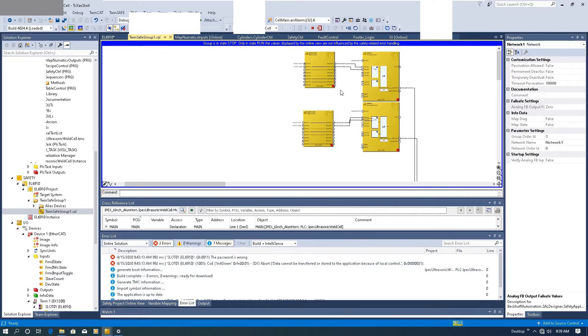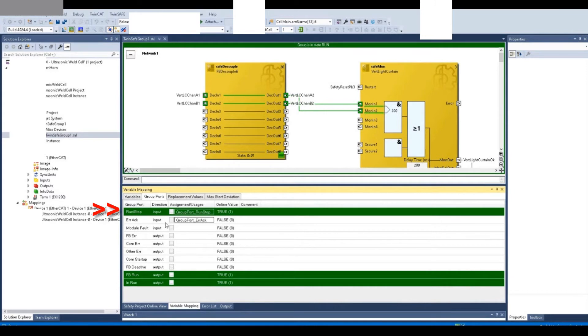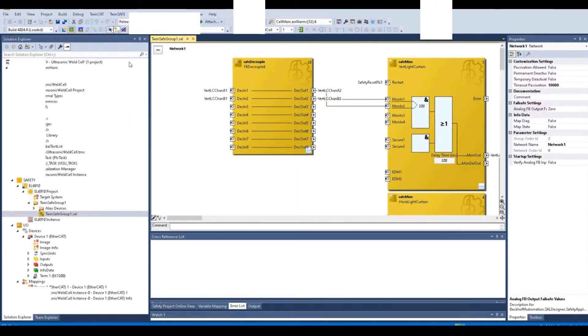Once you go online, if you see all the function blocks show a red flag, on the top area if it shows 'Stop' you must check the run-stop signal for your safety controller. This signal must be on to let your safety controller run. Keep in mind that the run-stop signal comes from the standard PLC — you must guarantee that the run-stop signal has been started.